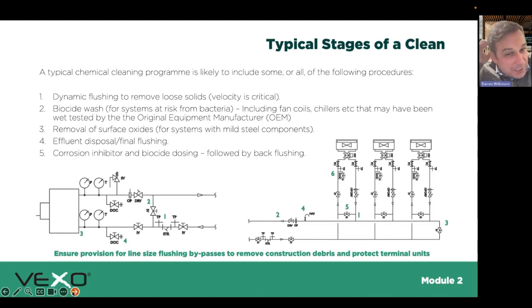Typically, biocide washes are used for systems at risk from bacteria. If you've got terminal units that are being wet tested, or even chillers that are wet tested, it's a really important question to ask the OEM, because if it's been wet tested, and I found a chiller once many years ago, before we opened it to the main system, and this is before we were in the world of making biocide washing a regular thing, we found about 4 inches of biofilm inside the chiller where it had been wet tested and sat on a dock somewhere for probably months.